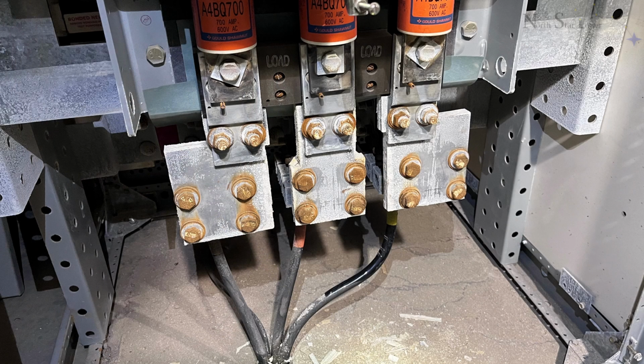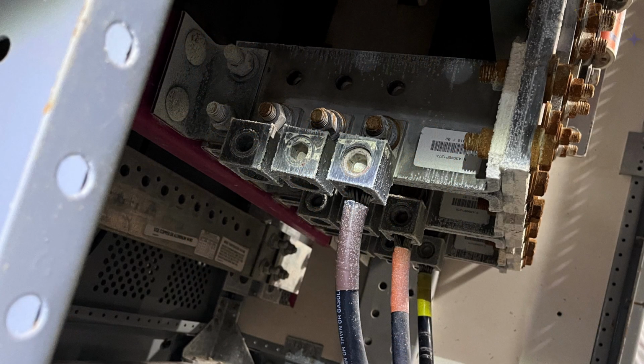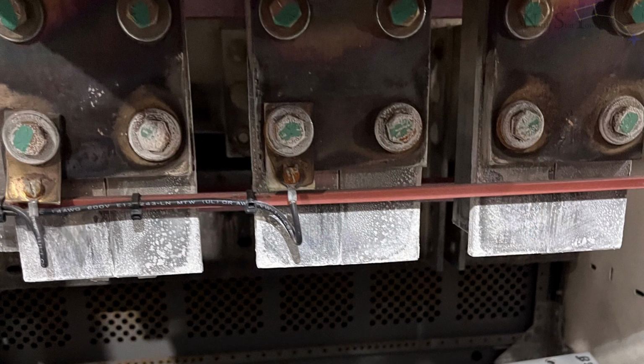If the air is corrosive, such as from nearby cooling towers, factory chemical use, or even salty air from nearby seawater, that will also cause rapid rust formation. Check cubicle panels for rust, pitting, corrosion, water damage, and missing paint. Check any ground cables to see if they are corroded or disconnected.